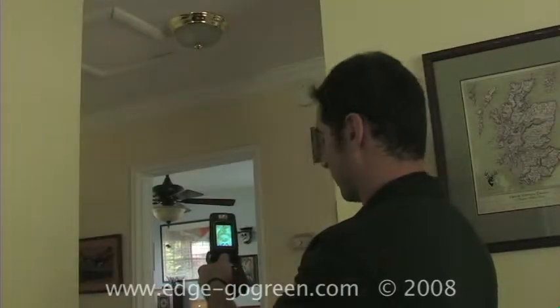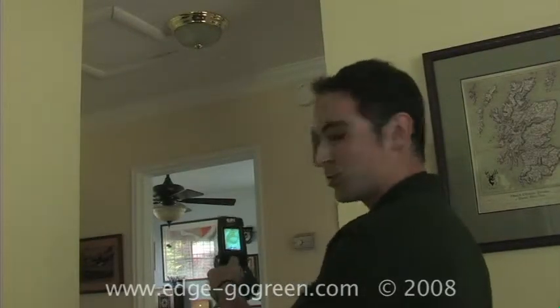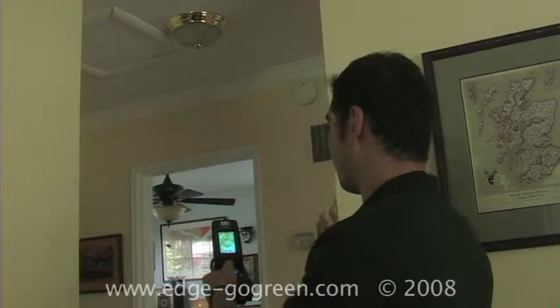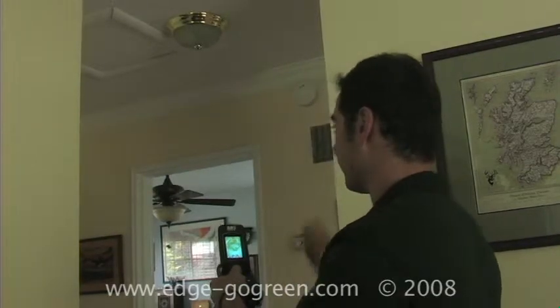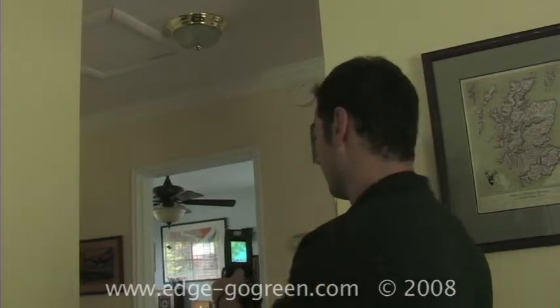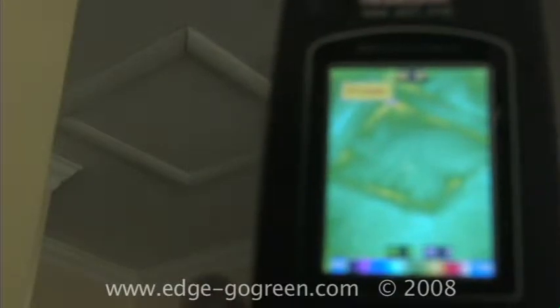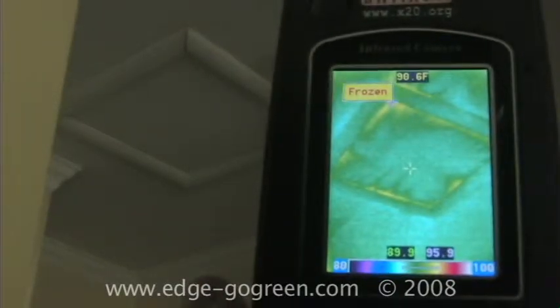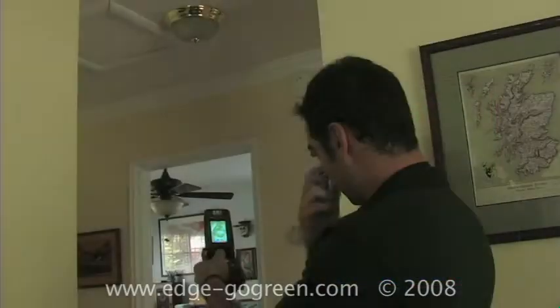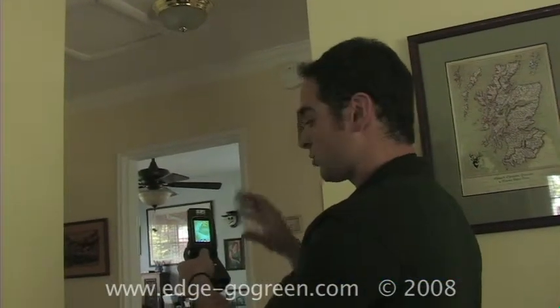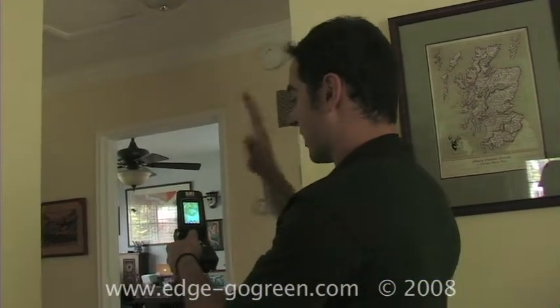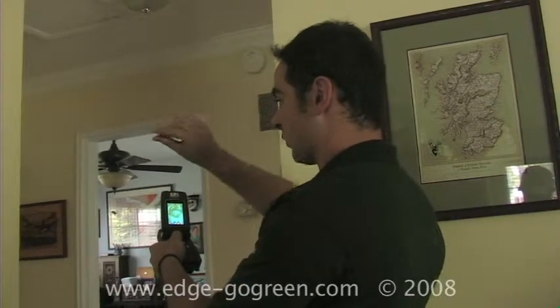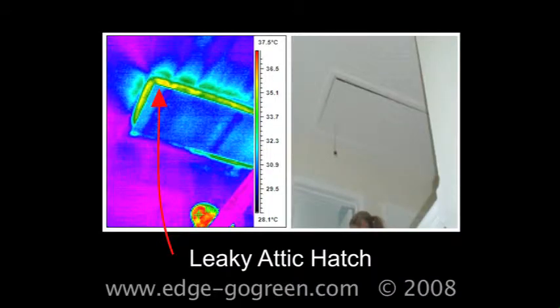What we're looking at is pretty much the leakiest object in the house, which is usually the attic hatch, pull down staircase, or any other access to the attic is usually the leakiest. There's simple fixes for this, just simple weather stripping and insulating the hatch will do the trick here. But one of the patterns we're looking for are any kind of streakage patterns. So if you see one area and then you see some air movement and you see little streakage patterns on that, we know that there's air movement coming in and around from that area.